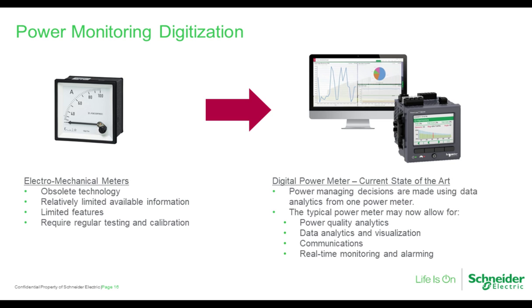We can manage decisions made using data and analytics from one power meter. The typical power meter may now allow for power quality analysis, data analysis and visualization, communications back to, again, a software system, and real-time monitoring and alarming. And again, this is just another device that adds to the system so that now you can take all this digital information and make comparisons of your system within the software. They can bring you, whether you have a power quality issue, whether you have a load issue, whether you have a demand issue, and all of these items added together with the other information that we're gathering from digital devices helps us make better decisions on how we run our processes, how we run our system, and what our loads and energy look like.